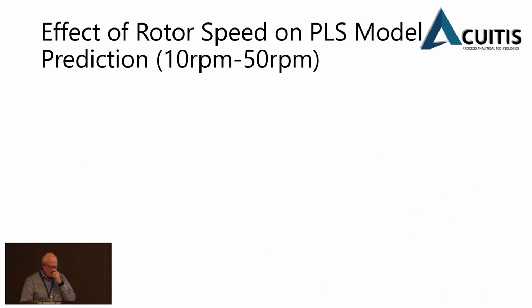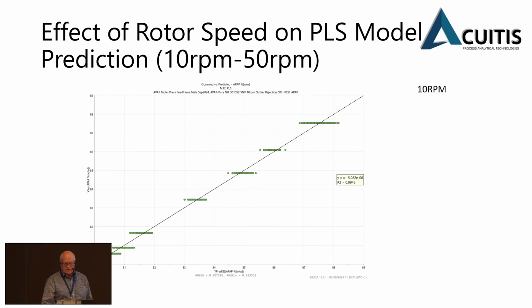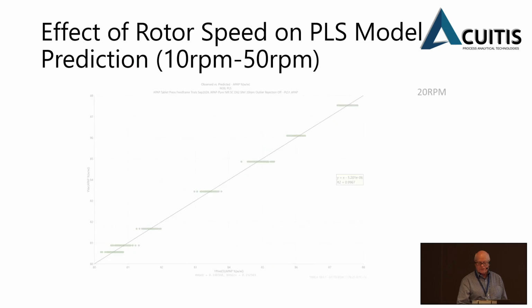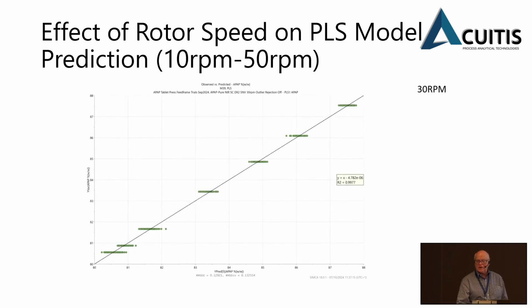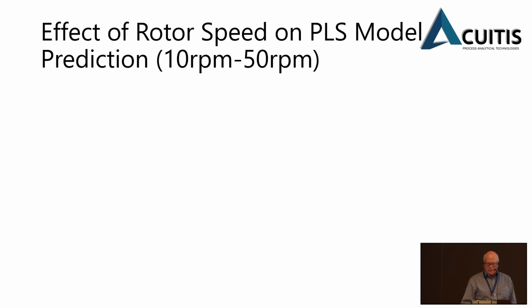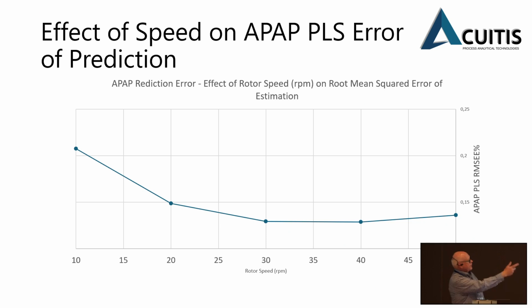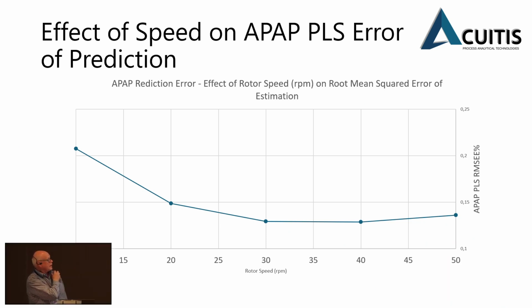In fact, this is some other work that I think Uwe and Phil did, looking at what happens if you change the speed of rotation of the paddle wheel. If you look, it starts off at 10 RPM, and if I flick through these quickly, you'll see as they change the speed, the prediction error decreases. But as you get further along, when you get to 50 RPM, it increases. So again, here's an indication that you need to empirically measure what the optimum rotation rate is to get the minimum error in a calibration. Here's a curve of those speeds of rotation against the error in the calibration performance.